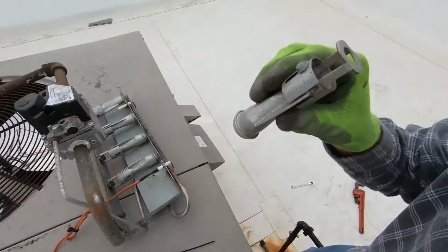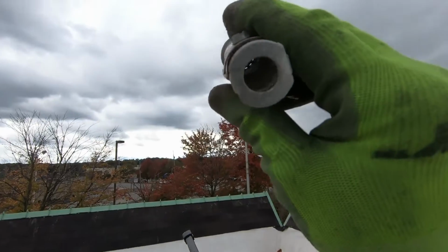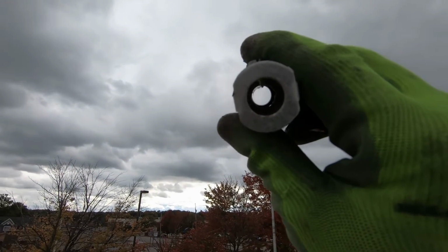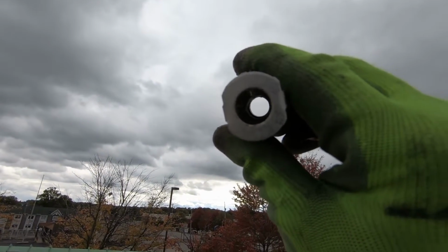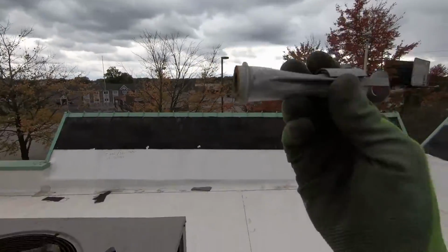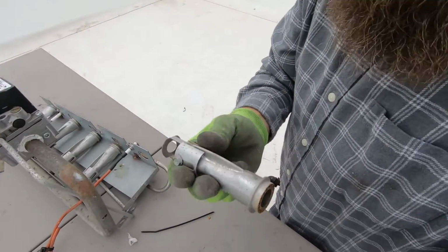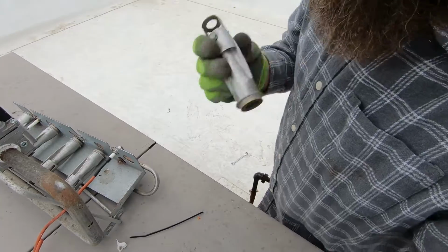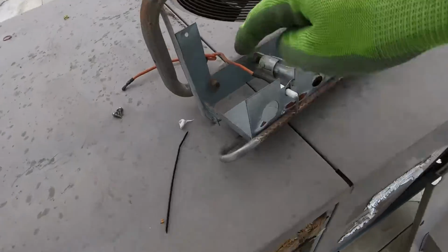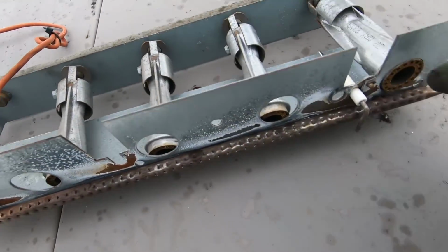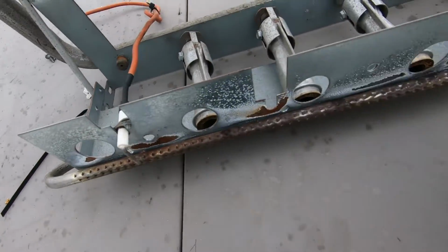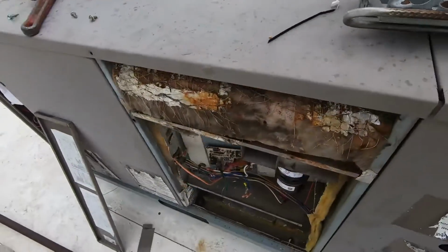So we've got our same burner here. Now we can see through it. I am going to take a wire brush to it. I'm going to clean it up. I'm going to blow it out with some nitrogen, but that's what caused our rollout, and that rollout switch did exactly what it was supposed to do. And just for good measure, I'm going to go ahead and check all these orifices. I'm going to brush off the carryover tube, all the burners, and then we'll get this thing put back in place.